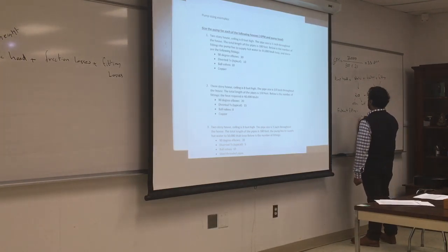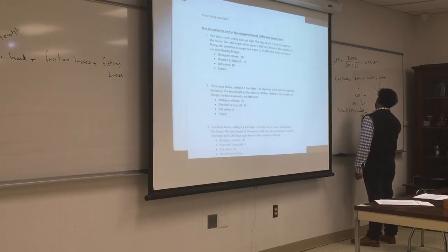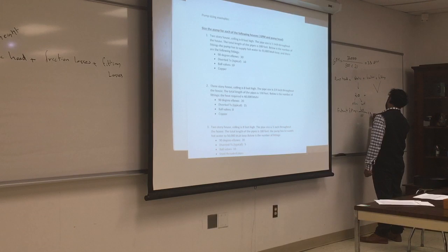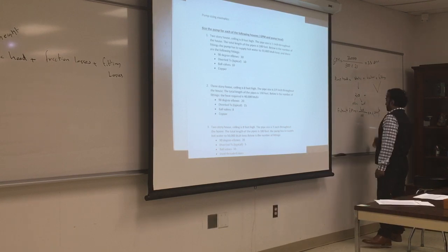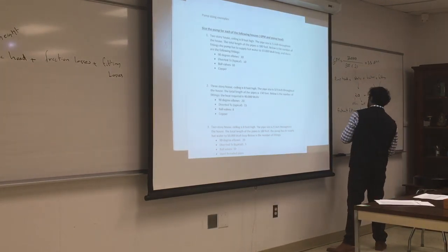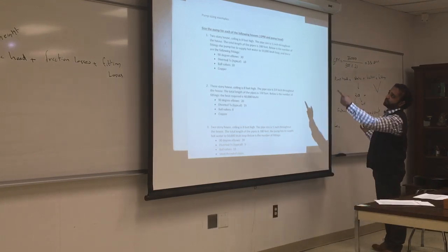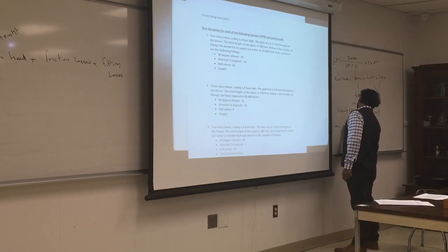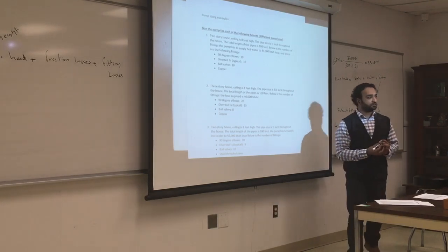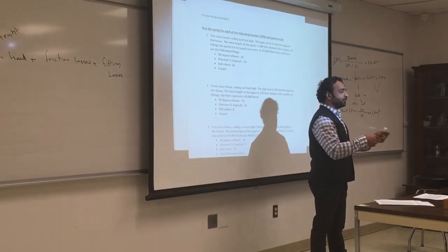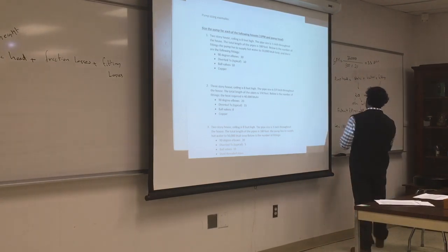Friction and fittings. So what is the equation? LE over 100 times A times GPM to the power B. In order to find the LE, that will be the total length of the pipe. What is the total length from the question? 180 feet. In real life, you'll go and measure the length in feet and estimate all the length for the project, and that's your length.